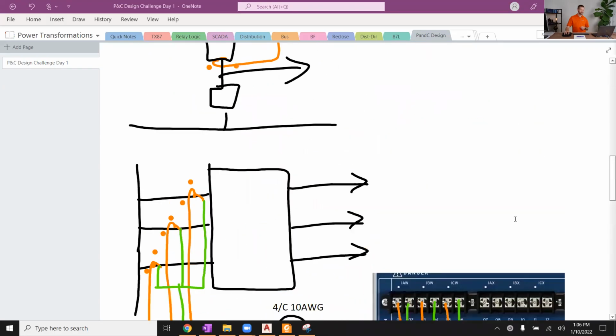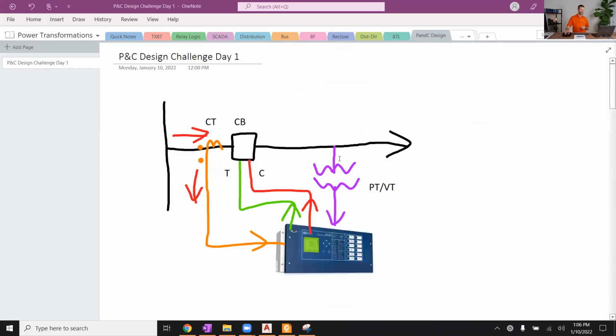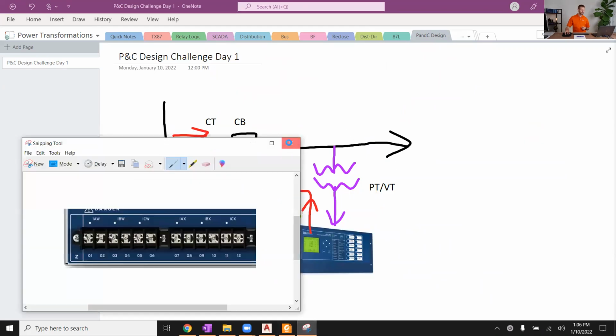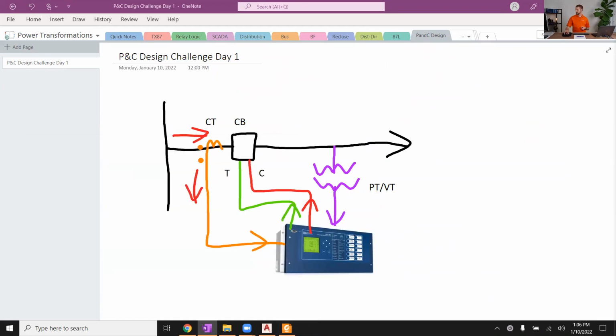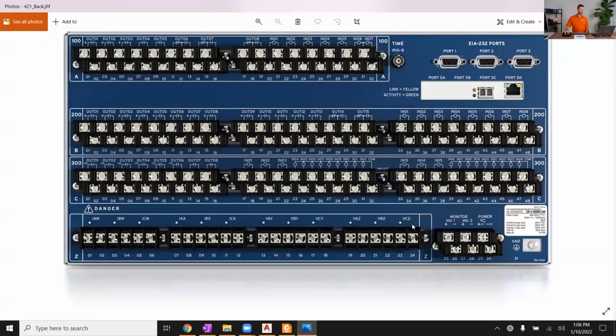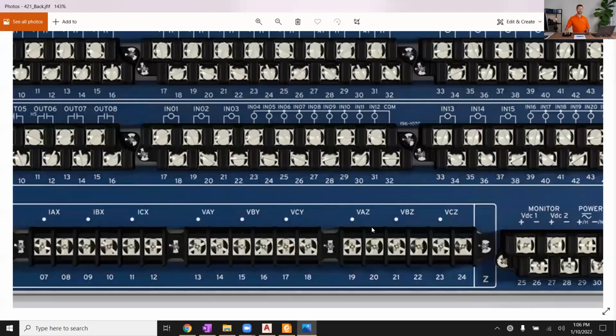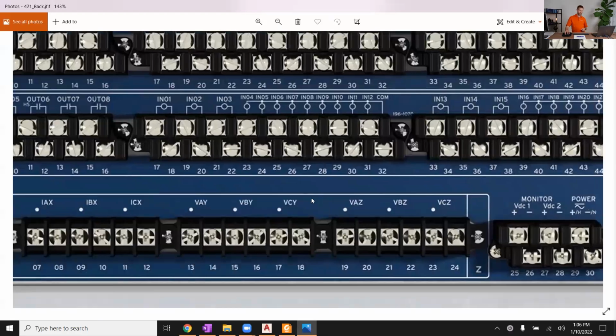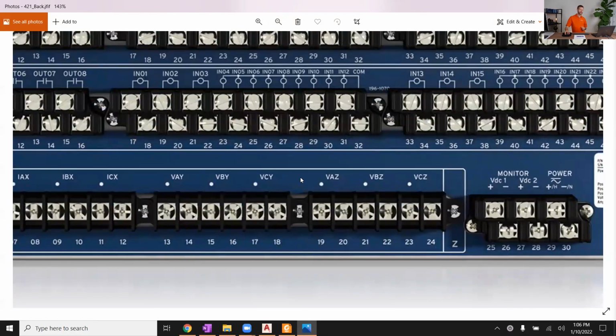We looked at the back of the relay up here. We showed, okay, we're going to wire the PTs in. We showed the back of the relay of a 421. We've got these two different voltage terminals, similar to how we had two current terminals. Why two sets? You might have three-phase line PTs, and then maybe you have bus PTs as well. Maybe you have a double bus, double breaker situation, or a breaker and a half, or a ring bus where you need some sync check voltage sources.